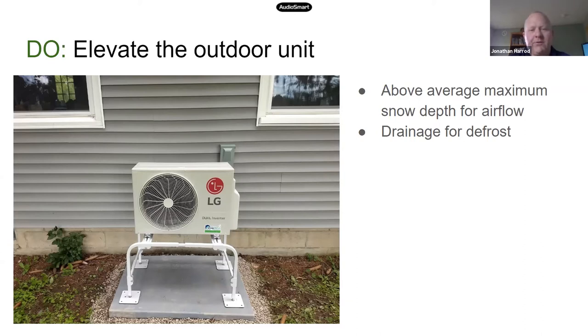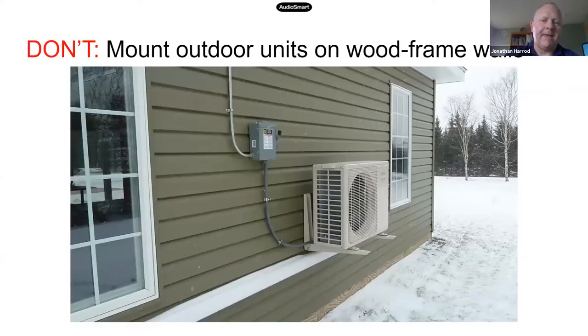That's why you need the free drainage under the unit. If that ice starts to build up, it will eventually block airflow through the unit, and in an extreme case could even crush the coils, leading to loss of refrigerant and kind of catastrophic damage to the system. So having that free drainage under the unit is really important.